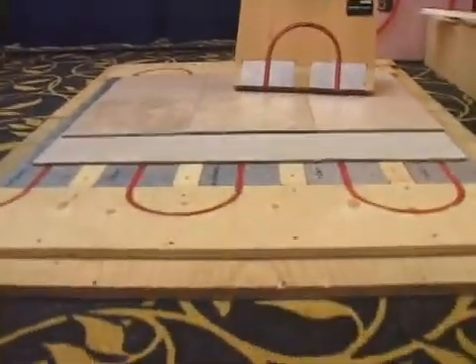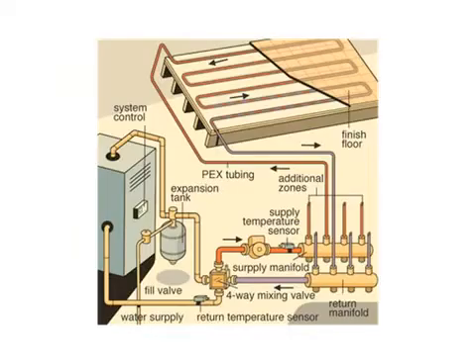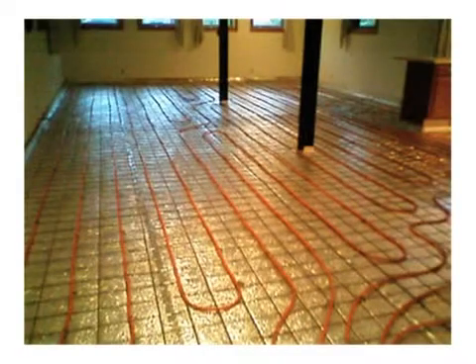Now, if you have, like, a basement that you want to add heat in, the raw panel product over here on the left is the best way to do that, as this goes on top of an existing floor. It's easy to install because they have all the product, the end plates and end pieces. The straight plates are 6 foot long, and the filler strips are pre-made. It uses a PEX tubing, and it's more money, but it's a higher performance.